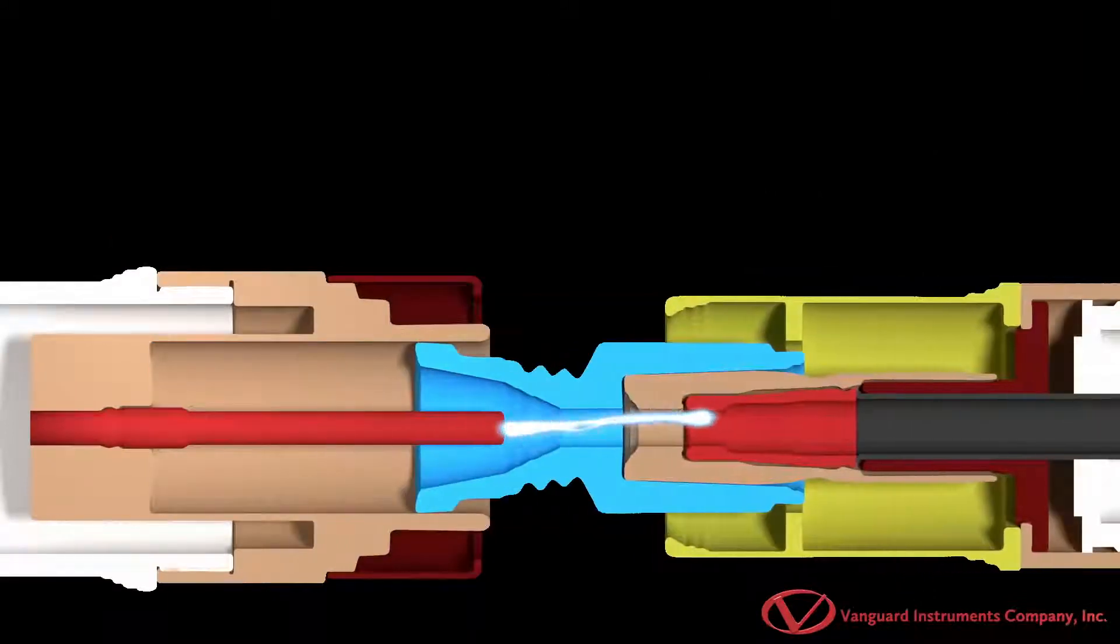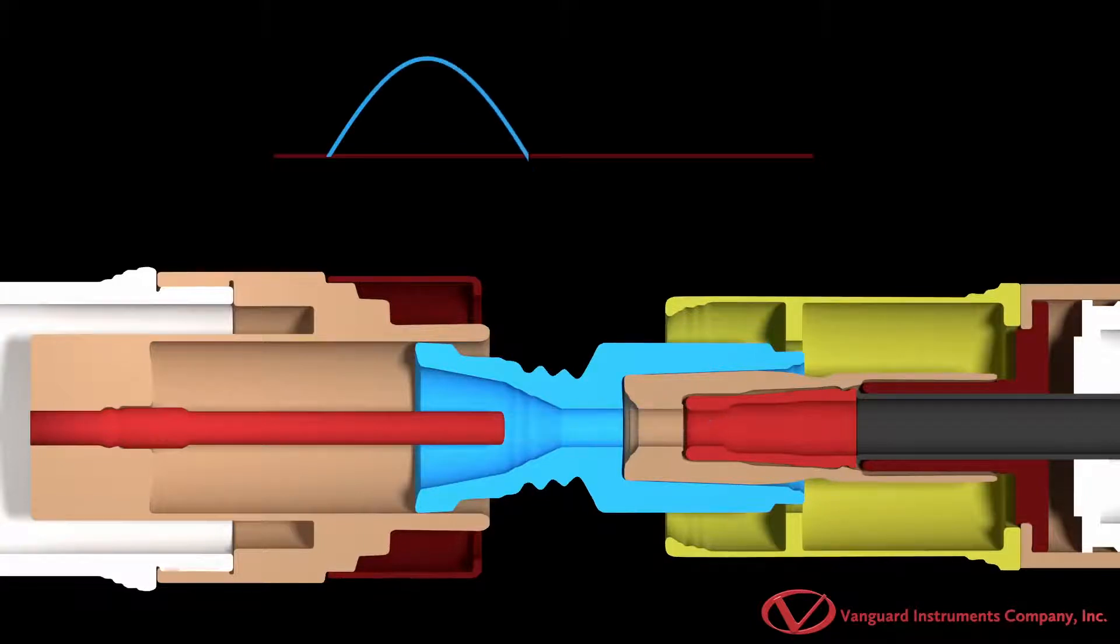When the contacts open, an arc is created due to current interruption. An AC arc extinguishes at every zero current level but reignites immediately after crossing the zero point due to the presence of voltage across the open contact.